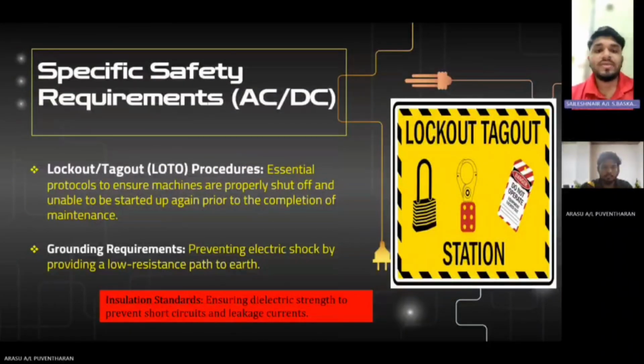The next slide is specific safety requirements, AC or DC. Now let's talk about physical safety. The lockout/tagout, LOTO, system is the most critical life-saving protocol. Before any maintenance on DC or AC machines, the energy source must be physically locked with a padlock and a tag must be placed. We also must emphasize grounding. In AC machines, a fault in the insulation can turn the motor casing into a live conductor. Proper grounding provides a low resistance path to the earth, tripping the circuit breaker and saving lives.